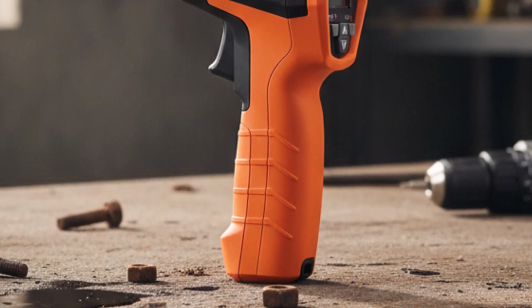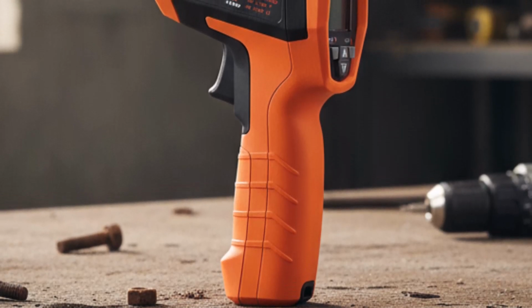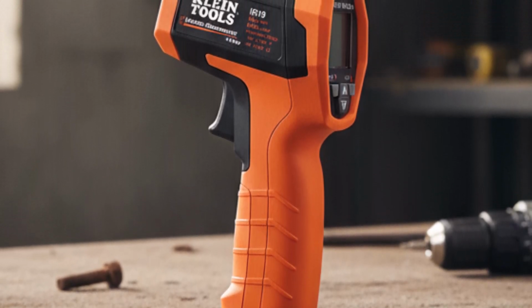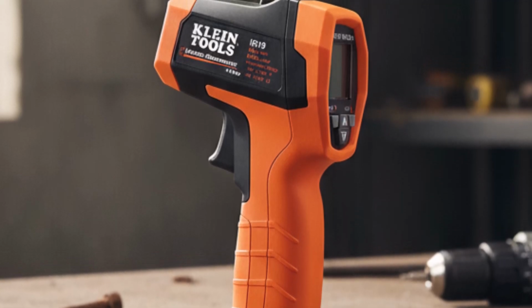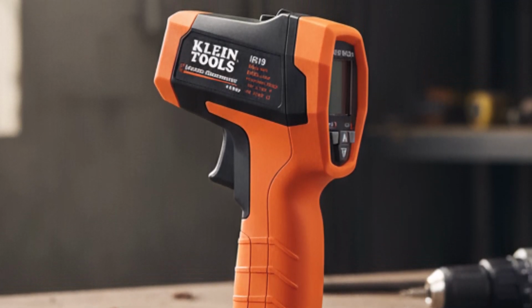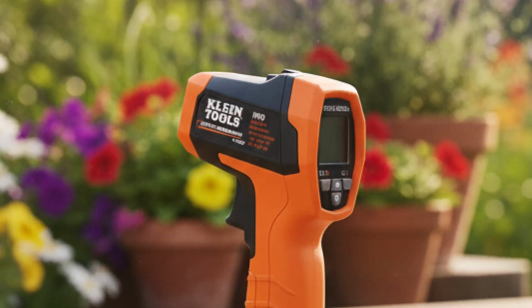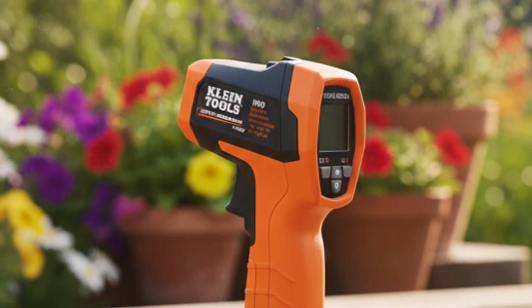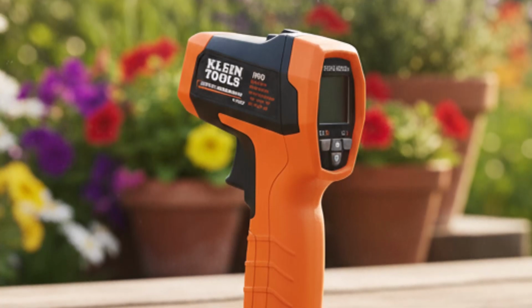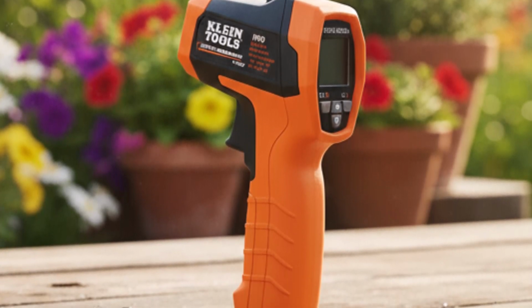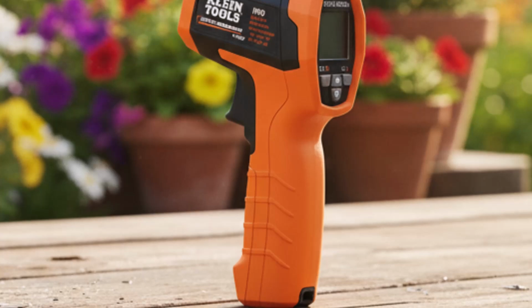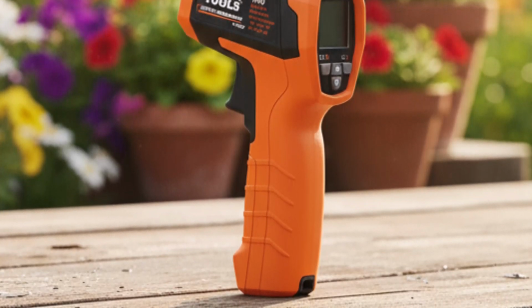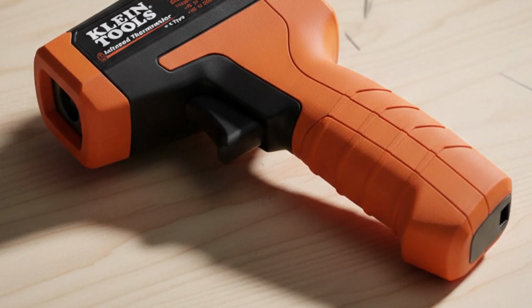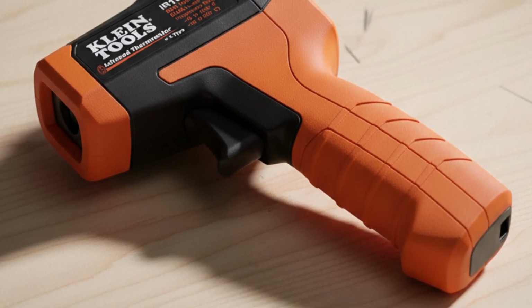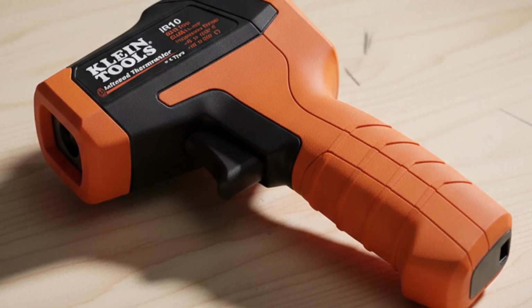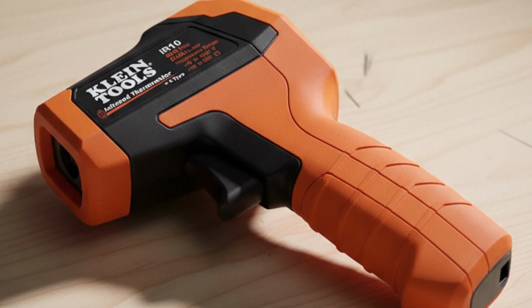One of its biggest advantages is the inclusion of a K-type probe, which enables both infrared surface measurement and direct contact temperature testing for air, liquids, or gas systems. Adjustable emissivity settings between 0.1 and 1.0 enhance measurement accuracy across different materials, such as metal, plastic, or painted surfaces. Dual laser targeting improves aiming precision, while advanced functions like auto scan, maximum and minimum tracking, differential readings, and high-low alarms provide deeper analysis during troubleshooting.